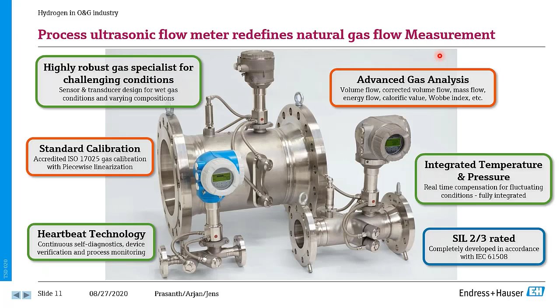Moving from Vortex flow meter to ultrasonic flow meter, this is our new process ultrasonic flow meter which we launched last year. Some of the key features on this device are SIL 2/3 rated, compliant to IEC 61508. As you see in the picture here, the device comes with integrated temperature and pressure devices, advanced gas analysis based on the speed of sound. For a known composition of gas, we can do calculations in terms of the energy content, the calorific value, Wobbe index in here.